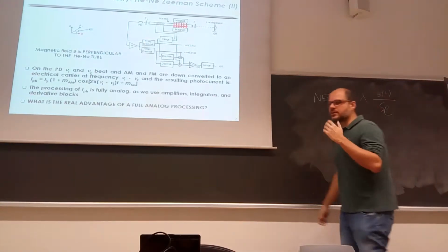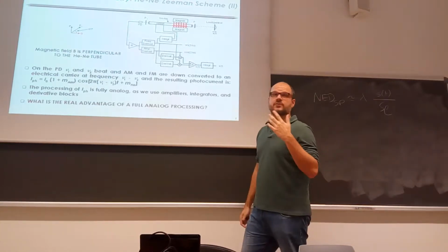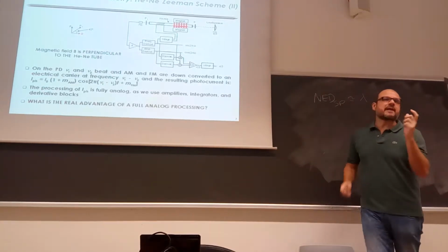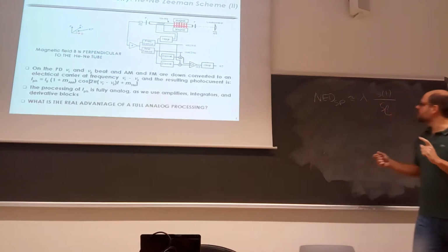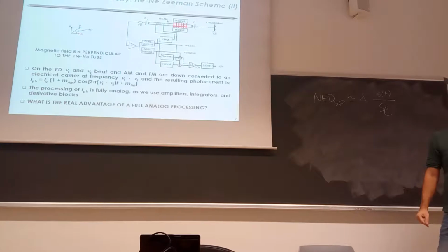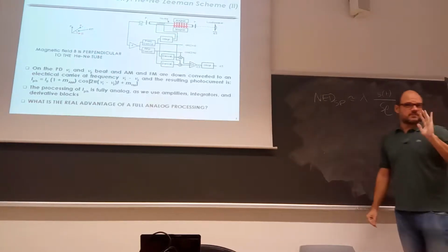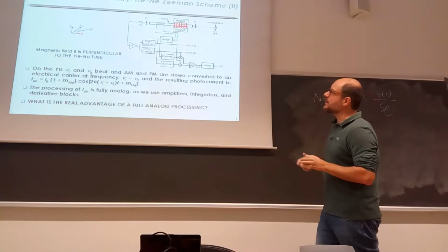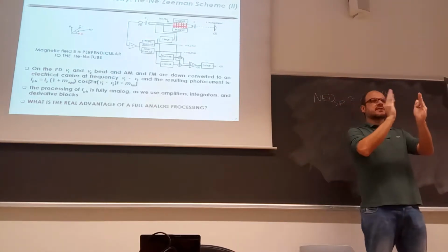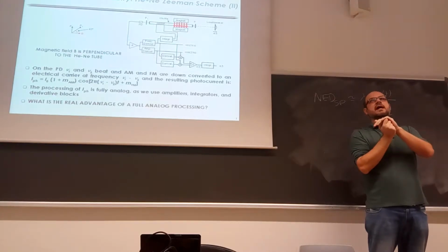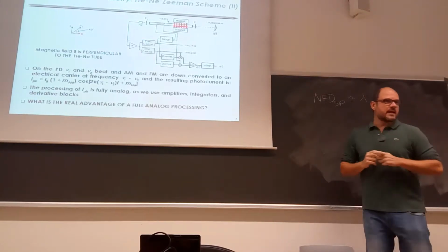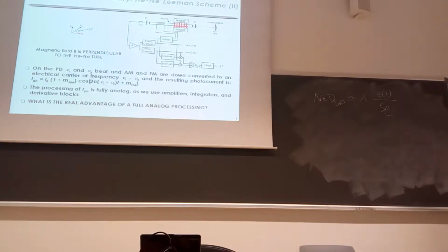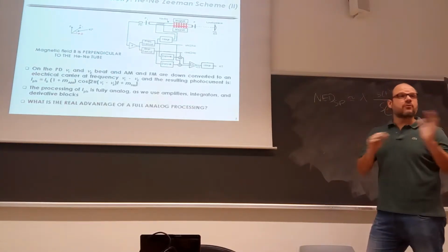So, in a way, if you work with the double beam interferometer approach, you know that you have a resolution that is more or less close to 80 nanometers. But it's hugely probable that you want to measure vibrations that are lower than 80 nanometers of amplitude. So, you have to find out another way to use this instrument. And in particular, if you use an analog approach, you don't have digitalization of measurement because you're not doing counting measurement. And so you can go deeply down to the real limits of measurement. So this is the idea behind the use of a full analog approach.